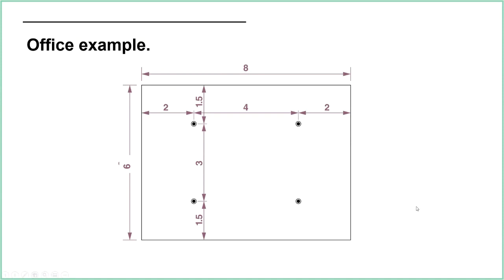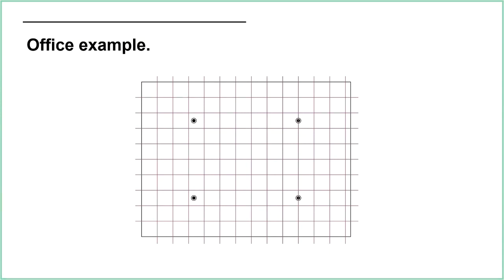Of course, that doesn't happen much in reality because we have obstructions to deal with. One example is a ceiling grid. I've put a ceiling grid on top of that head placement and you can see two of my heads are slightly off-center. Ceiling grids are typically 600mm x 600mm squares. The other two sprinkler heads end up on the join of two ceiling tiles. Generally, people want sprinkler heads in the center of a tile.